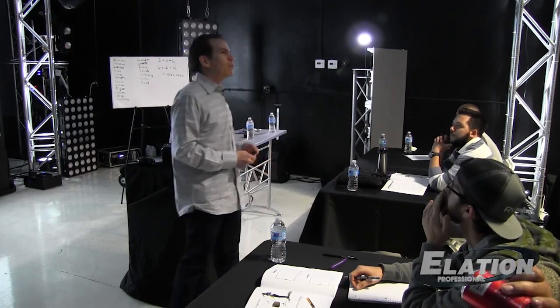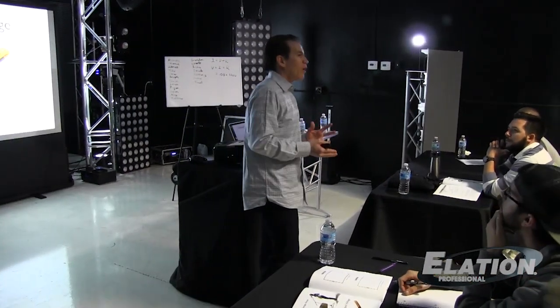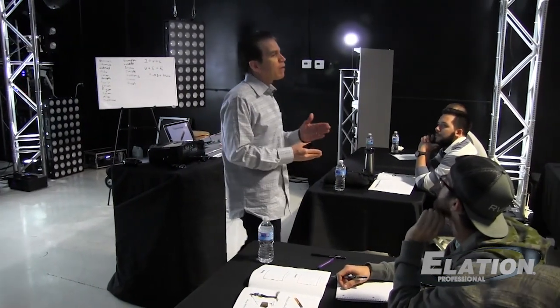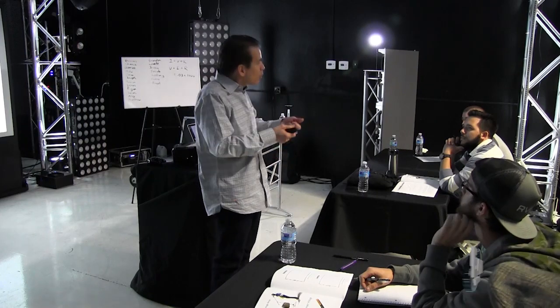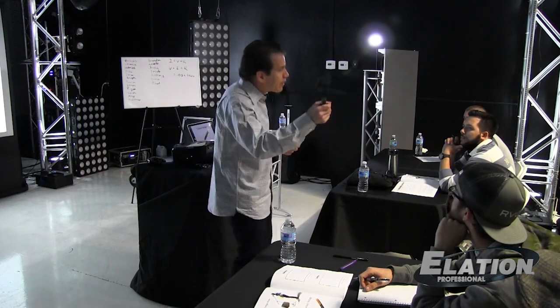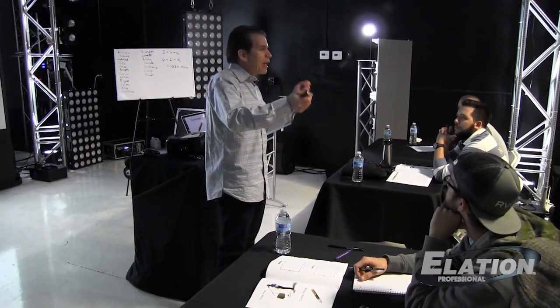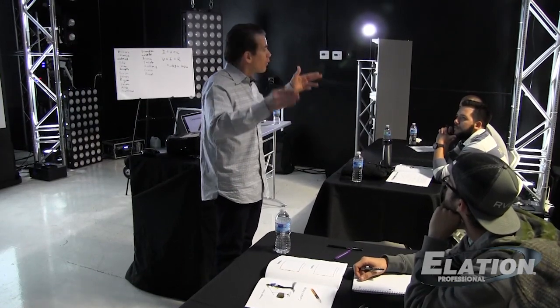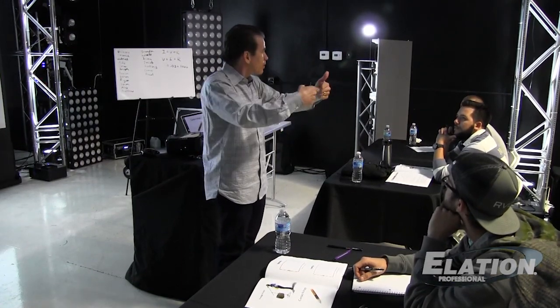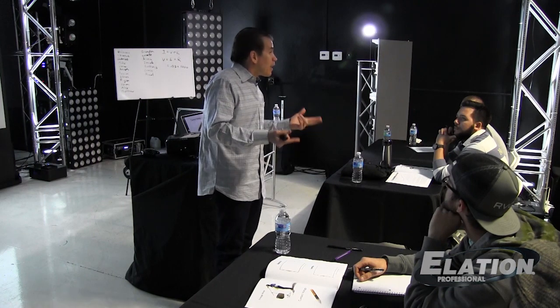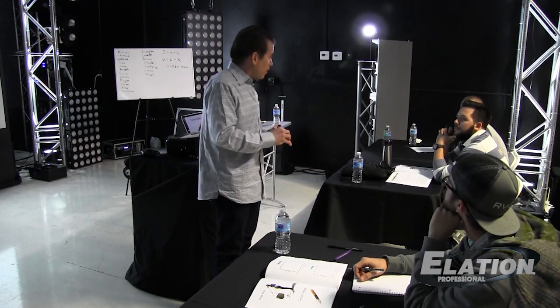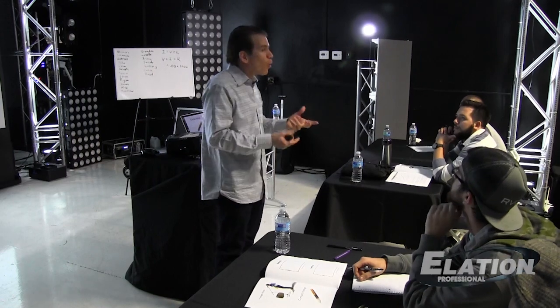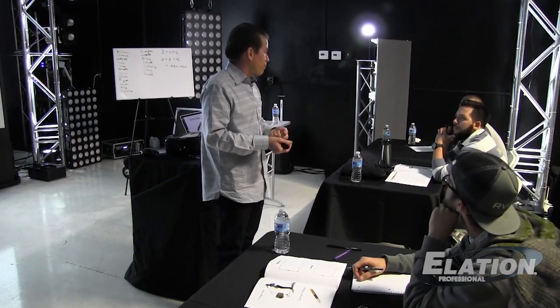If it's, say, a microphone, then chances are it's a faulty ground. You've got to go to the amplifier that's powering that device and look at the ground. The next thing I'll do is take my ohm meter and check for continuity between the chassis of the amplifier and any grounded piece of metal, the building steel, a piece of truss, to see if there's continuity. If there's not, that means you either have a broken green grounding conductor or a pin on the connector, or somebody purposely lifted the ground.